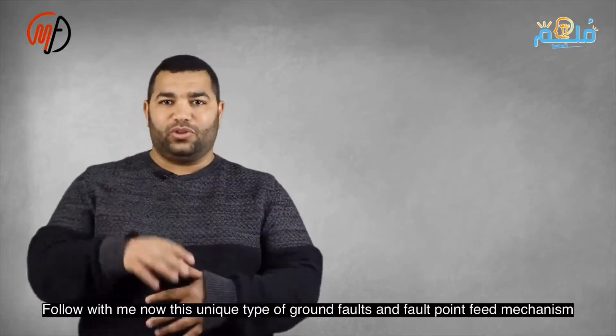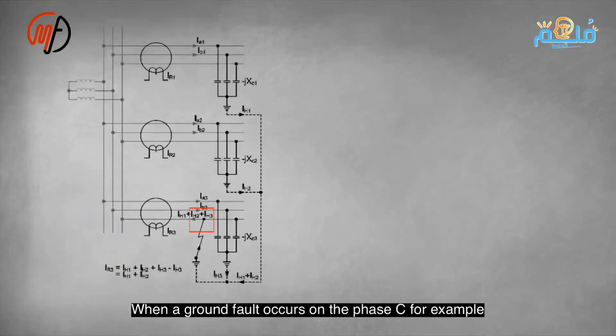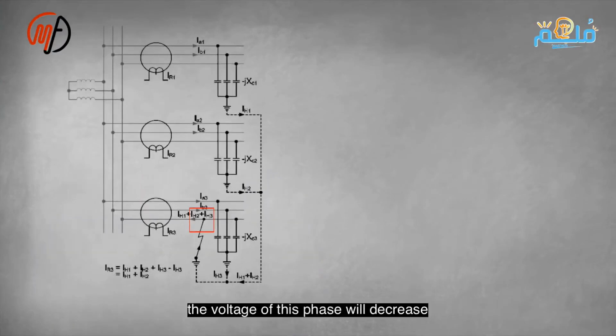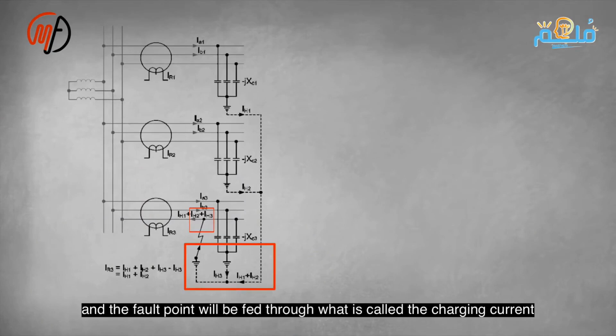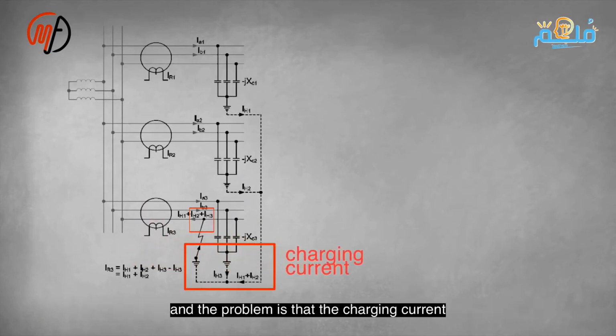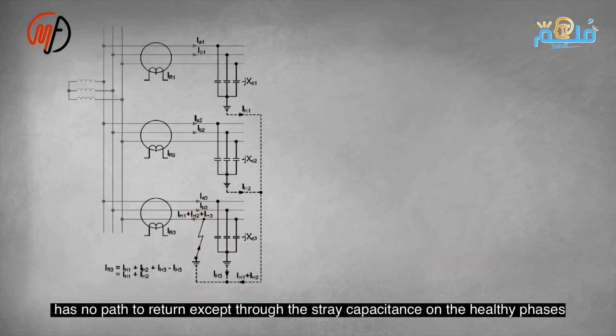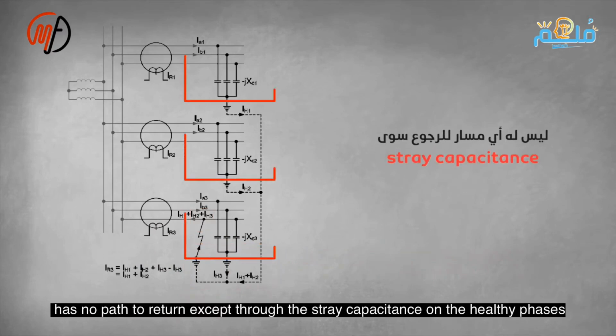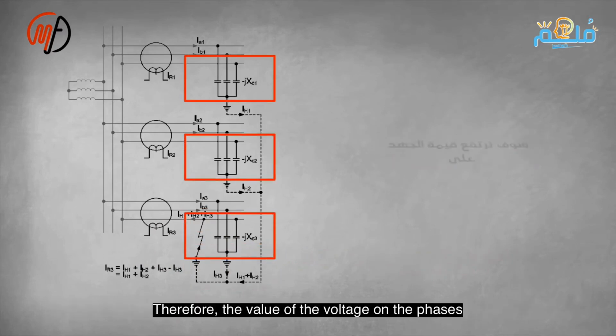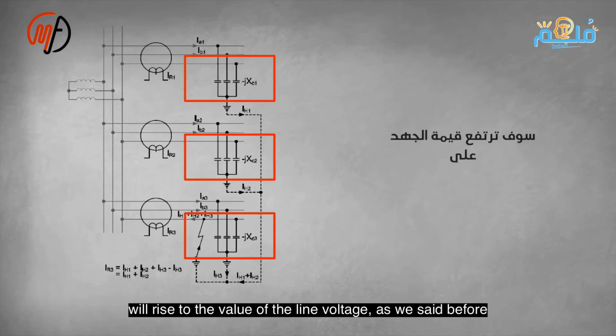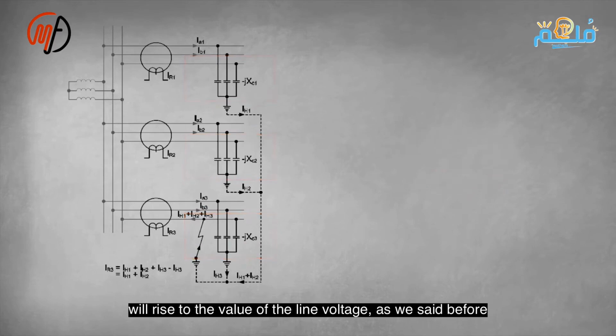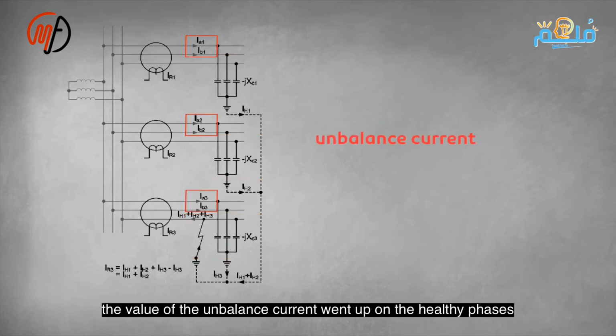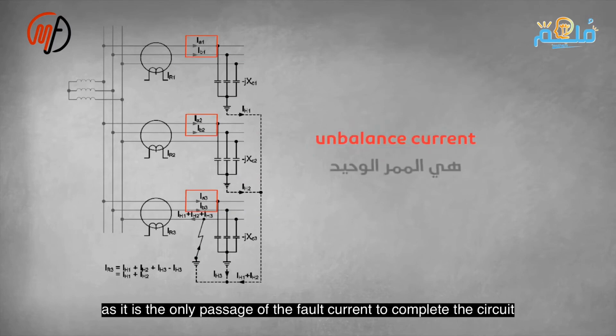When a ground fault occurs on a phase, for example, the voltage of that phase will drop. The fault point will be fed through what is called the charging current. The problem is that the charging current has no return path except through the capacitances on the healthy phases. Therefore, the voltage values on the healthy phases will rise after the fault happened. Now, the faulted phase reaches zero normally, as it is the only passage of the fault current to complete the circuit.